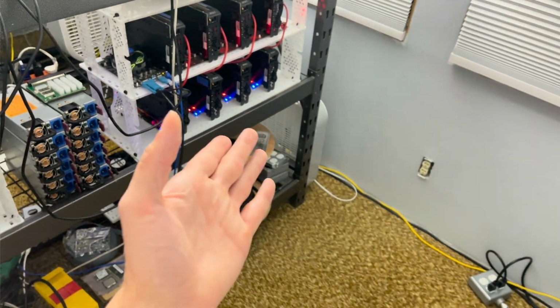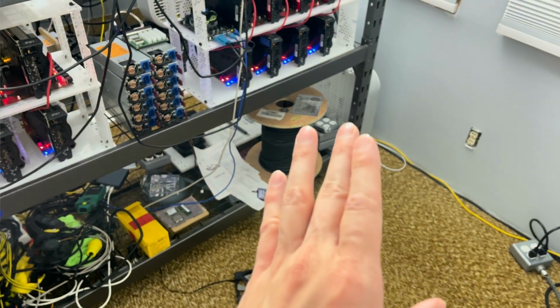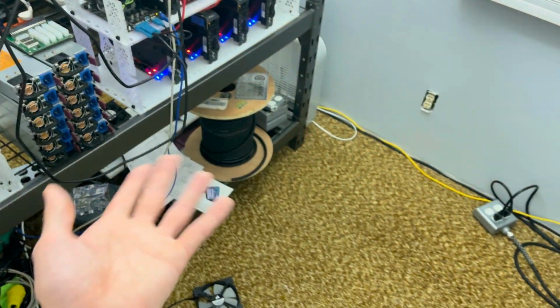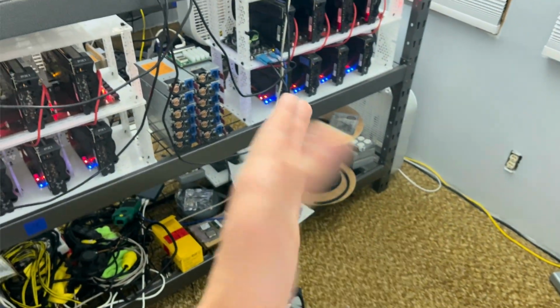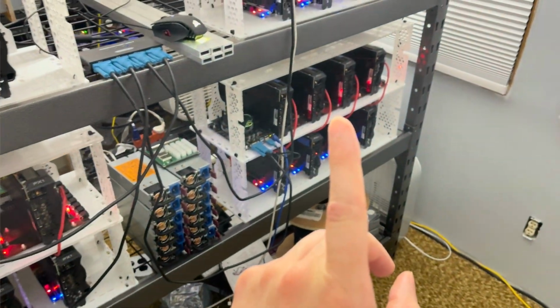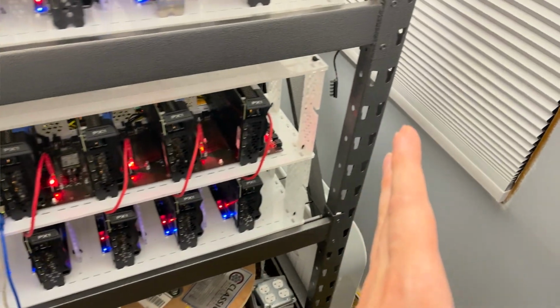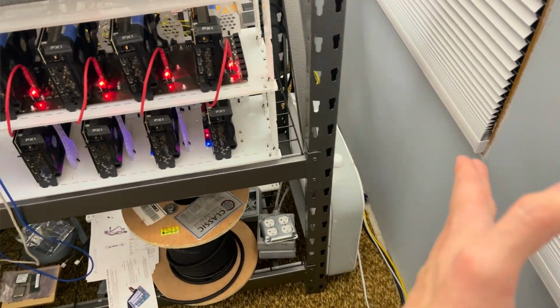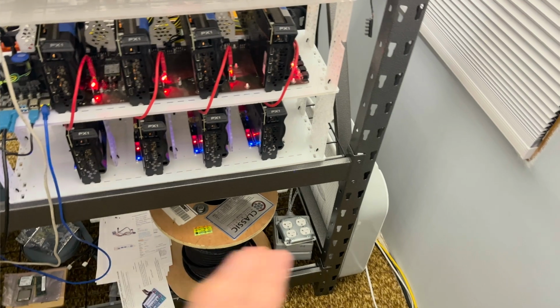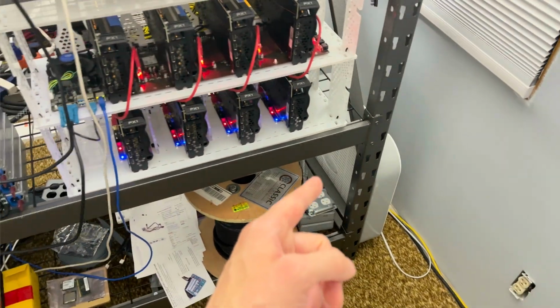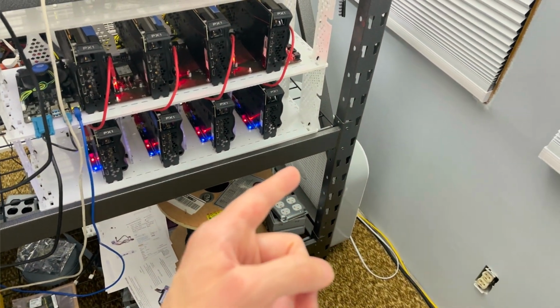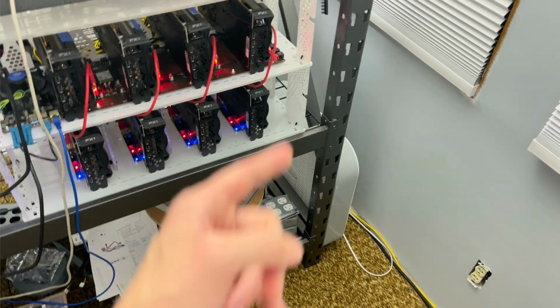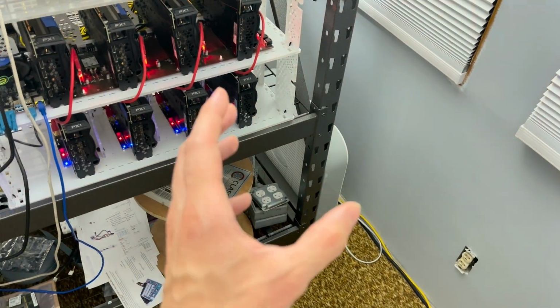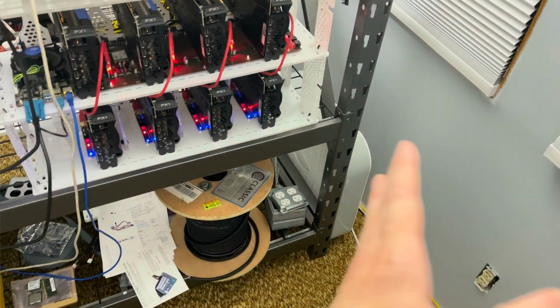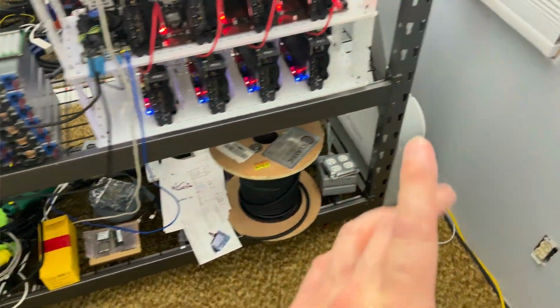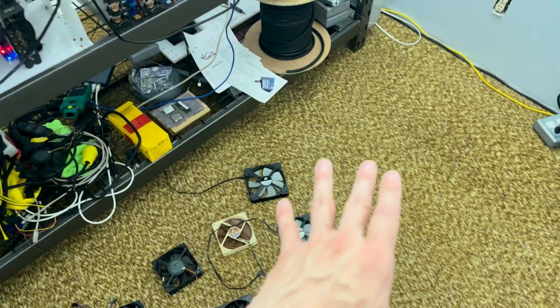So you may think I have 3000 CFM because I have a box fan, but it might only actually be delivering 400, 500, 600 because of your environment. And why is that? Static pressure. The filter will cause this fan to struggle to be able to pull air in or push it out. The motor isn't sized to be able to push more power. And the blades, the pitch, the design of the fan isn't designed to push against resistance. They're made and optimized for free air sitting in the middle of a room.